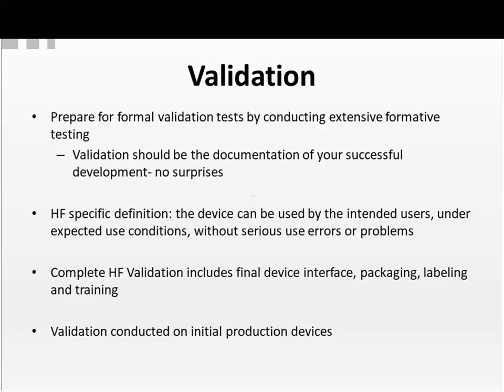The definition of validation, a human factors validation, is much different than a technical validation, software or hardware validation. The definition of a validation for human factors is that the device can be used by the intended users under expected use conditions without serious use errors or problems.